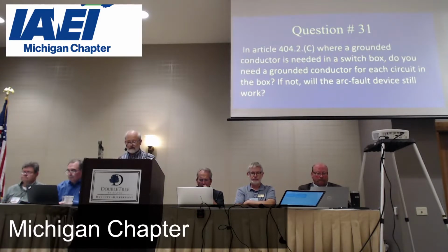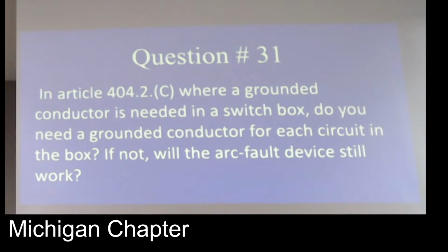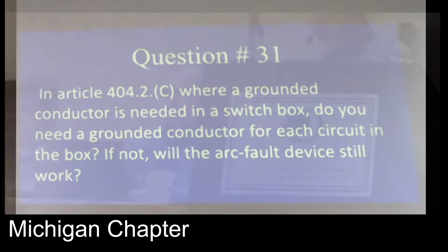Okay, Tom, Article 404.2(C), where a grounded conductor is needed in a switch box. Do I need a grounded conductor for each circuit in the box? If not, will the arc-fault device still work?